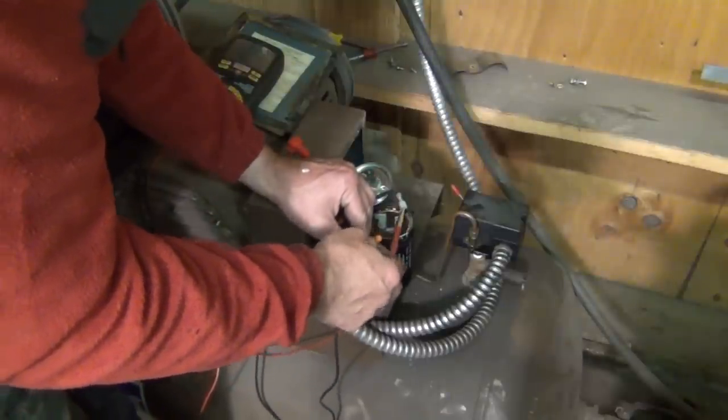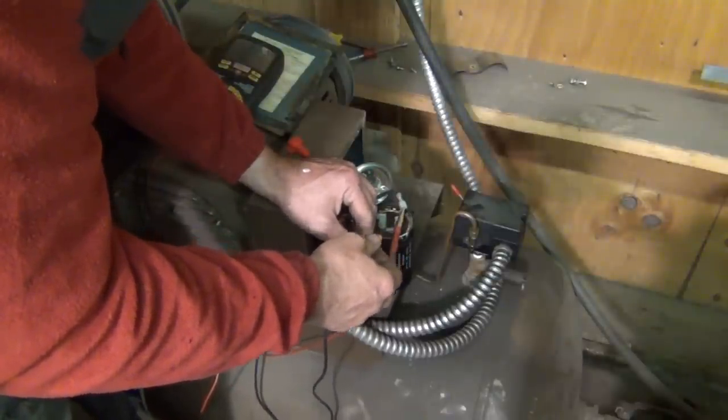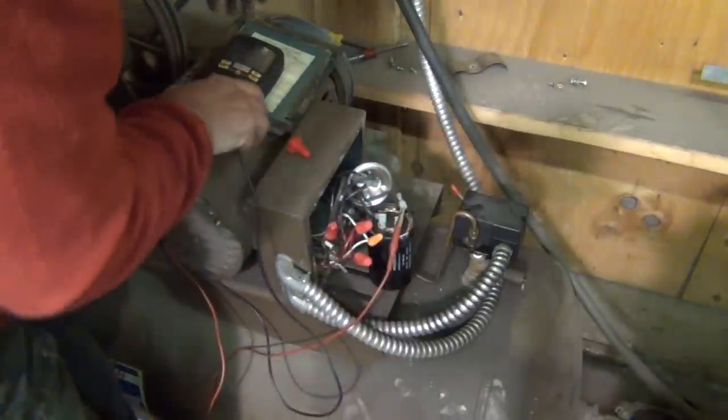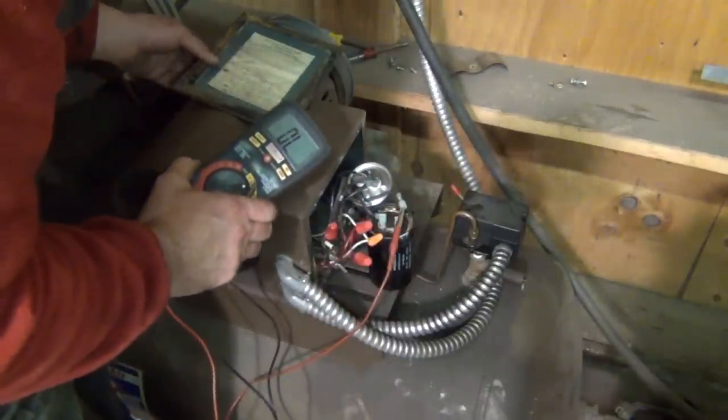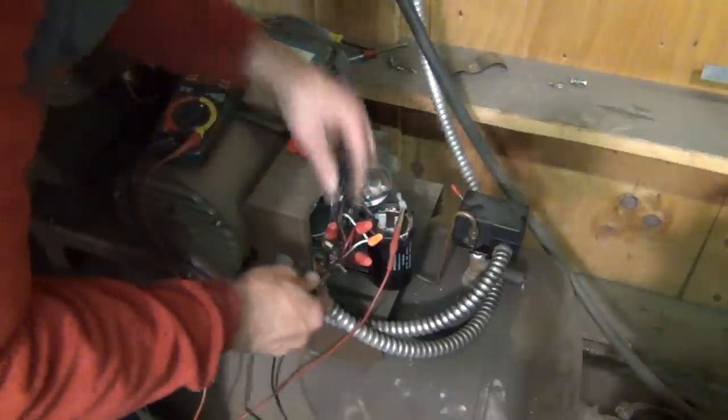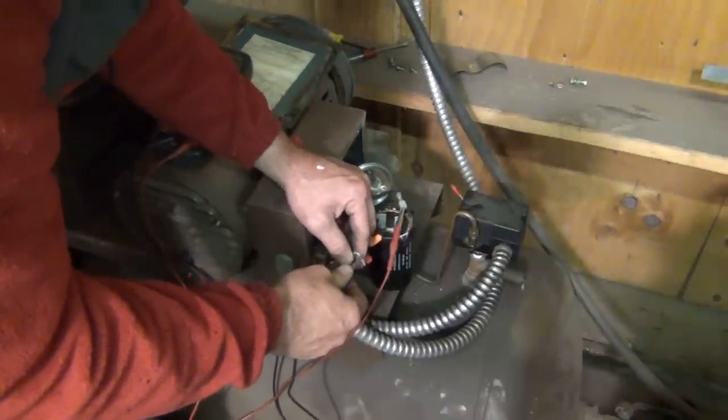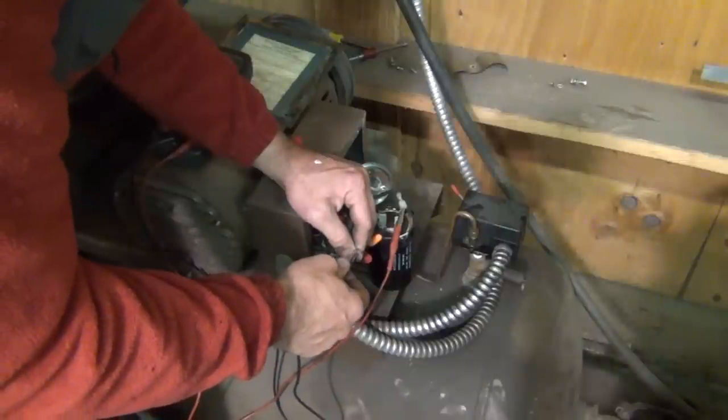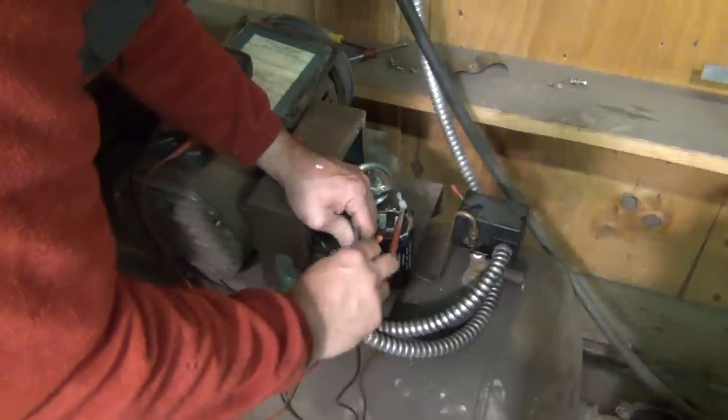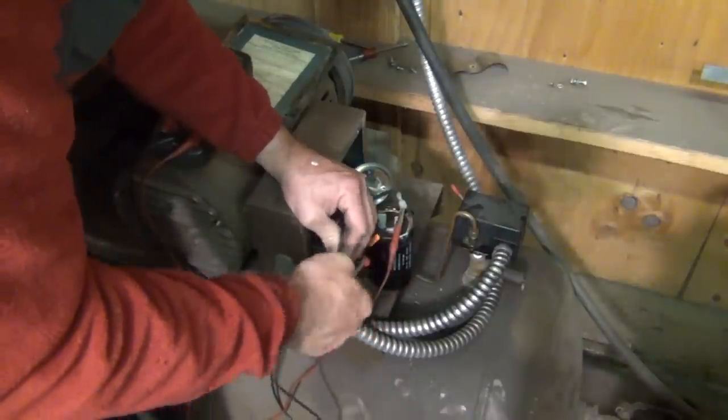When the motor stopped, that switch should be closed. Let me just double check my diagram here. L1 to T5. Huh. Well, usually it's the capacitor that's gone bad, but I think, maybe in this case, it's actually our inertia switch.